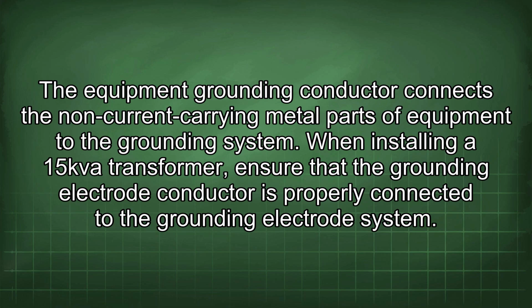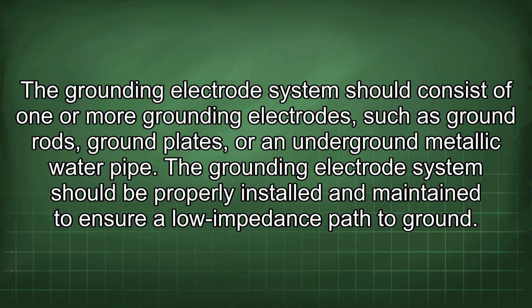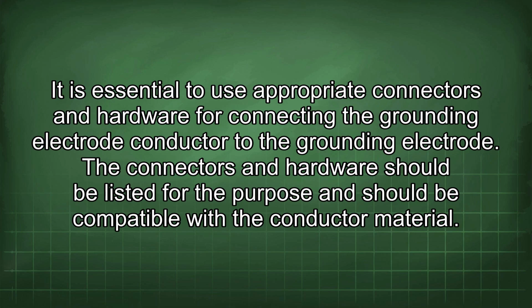When installing a 15kVA transformer, ensure that the grounding electrode conductor is properly connected to the grounding electrode system. The grounding electrode system should consist of one or more grounding electrodes, such as ground rods, ground plates, or an underground metallic water pipe. The grounding electrode system should be properly installed and maintained to ensure a low impedance path to ground. It is essential to use appropriate connectors and hardware for connecting the grounding electrode conductor to the grounding electrode. The connectors and hardware should be listed for the purpose and should be compatible with the conductor material.